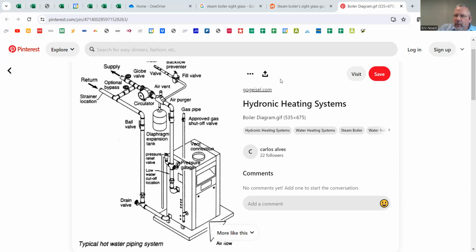The water in a boiler, we really want that to be dead water. We want there to be no air in that water whatsoever. The value there is that when there is no air, it slows corrosion. So the internal parts of the boiler and the radiators and the piping and everything are going to last longer when we've eliminated the air from that system. When air continually gets reintroduced, there's a higher potential for corrosion and breaking down of those parts over time. So our goal is to fill the water. When the water goes in, it should go in at the vent, so it picks off some of that air to begin with. And then as the boiler continues to run, it's going to pull more and more of that air out of there.